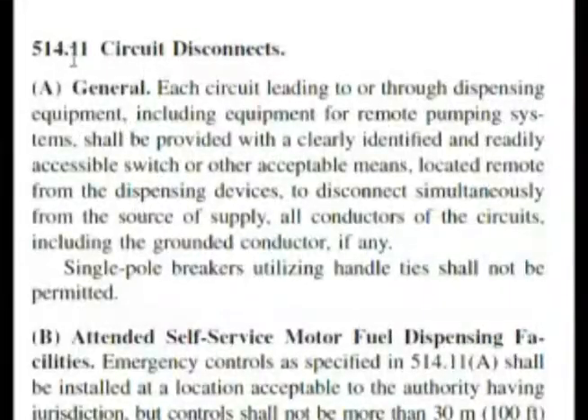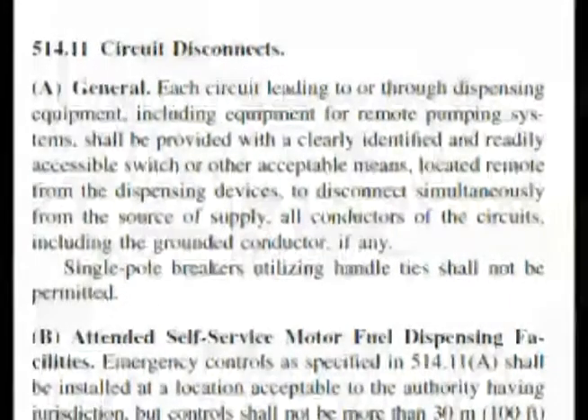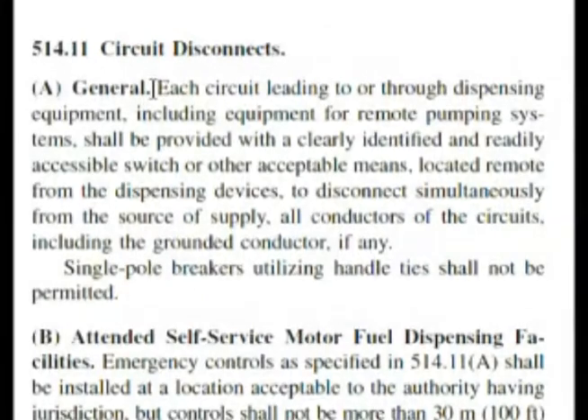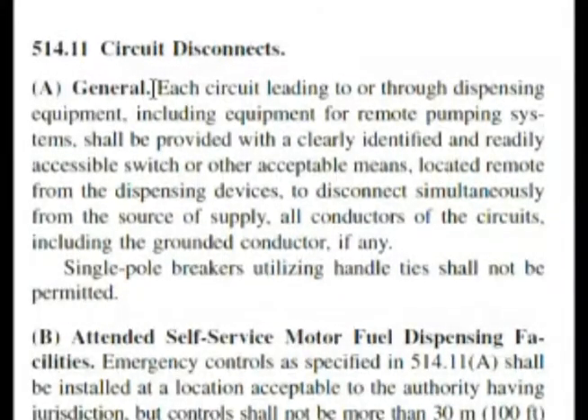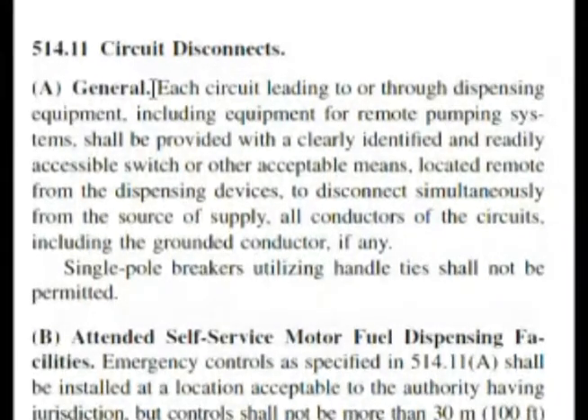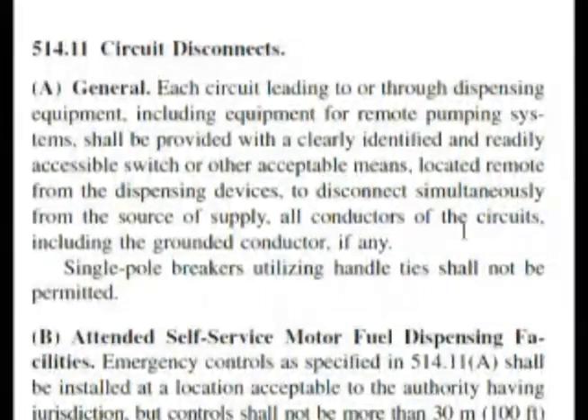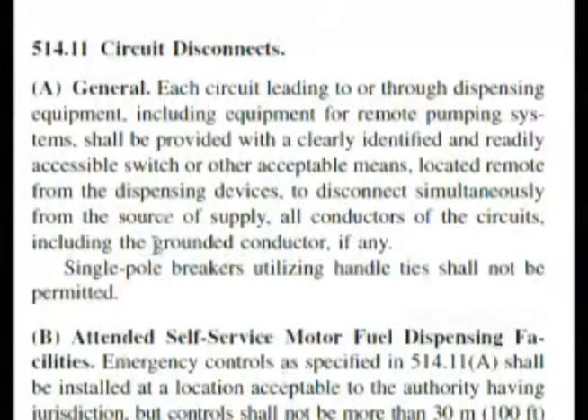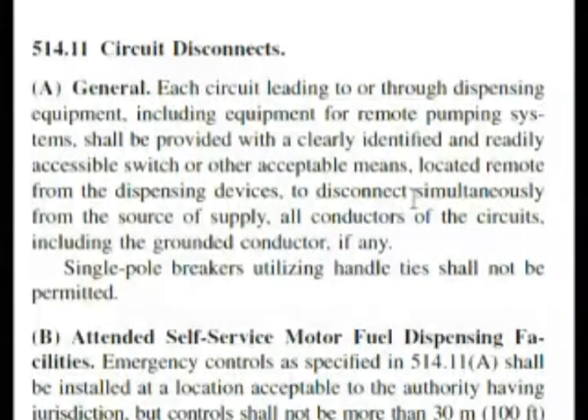Here we are at 514.11, Circuit Disconnects. 'Each circuit leading to or through dispensing equipment, including equipment for remote pumping systems, shall be provided with a clearly identified and readily accessible switch or other acceptable means, located remote from the dispensing devices, to disconnect simultaneously from the source of supply all conductors of the circuits, including the grounded conductor, if any.' This is nearly word-for-word our question, but the question left out that the disconnection must be simultaneous.